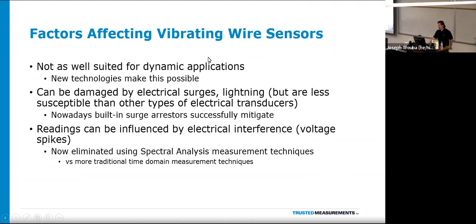on that frequency. They can be damaged by electrical surges, such as lightning, but they're less susceptible than other types of electrical transducers. Nowadays, we build in surge arrestors into the instrument itself, and typically people will add lightning protection to the instruments, which mitigates this issue.